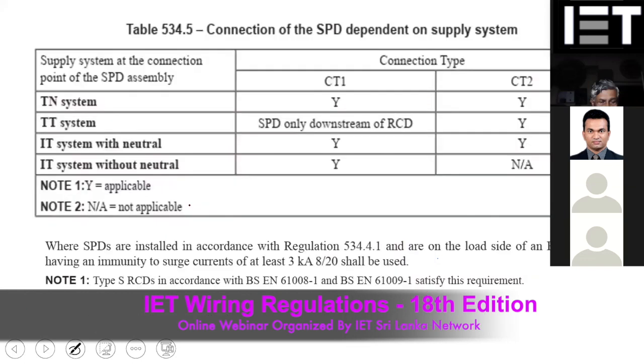But for the TN arrangement, you don't need to worry about that. In the TN arrangement you have the PE conductor, so the fault current will flow to the PE. The fault current will not be as small as in the TT arrangement. So if we can confirm that the upstream protective device can detect that type of fault, you can go ahead with this type of connection for the TN system. But for the TT system, this is not recommended if you are using it before the RCD. If you are using it after the RCD, then you can go ahead with this type of arrangement as well.